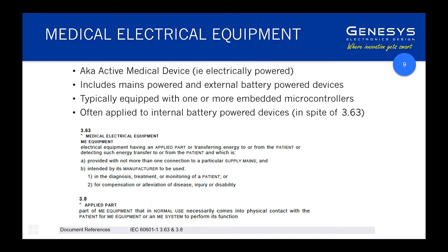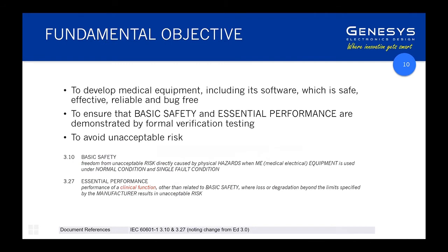Typically you're dealing with devices with embedded microcontrollers, and that brings into play the relevant software standards called up by 60601-1. That's why we call it the Active Medtech community — devices with embedded microcontrollers, batteries, and power sources are 'active.' You can actually have medical devices with energy sources other than electricity, but they're very few and far between. There are also many aspects of this standard applicable to non-electrically powered devices.